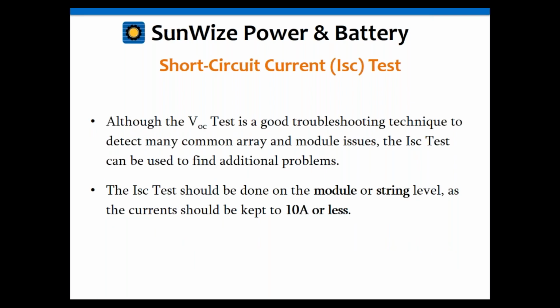And again, although the VOC test, the open circuit voltage, can tell you many things, there are a few times when the short circuit current test can tell you some stuff. A loose connection is a good one. I had a tech support call probably about 9 months ago or so, where it was a loose connection at a junction box. It was a 5-year-old system, I think, something like that. And again, the thermal cycling had caused the loose connection. It was reading fine on the VOC test.